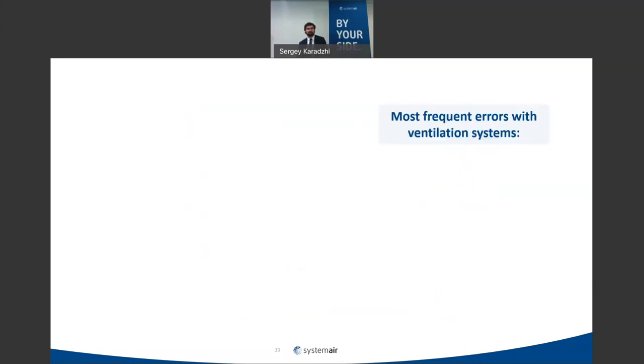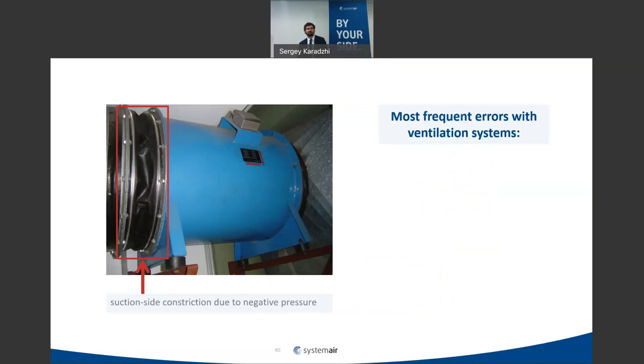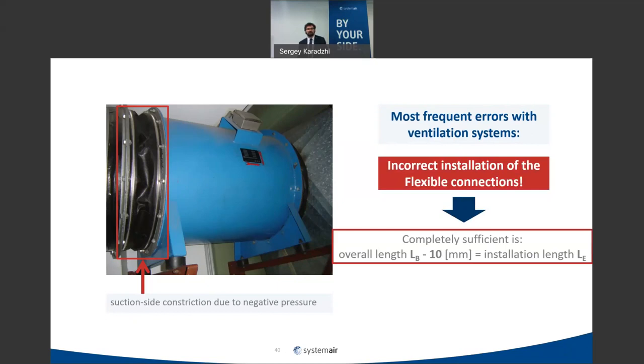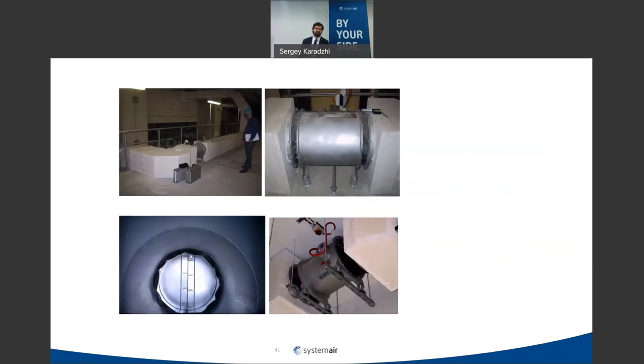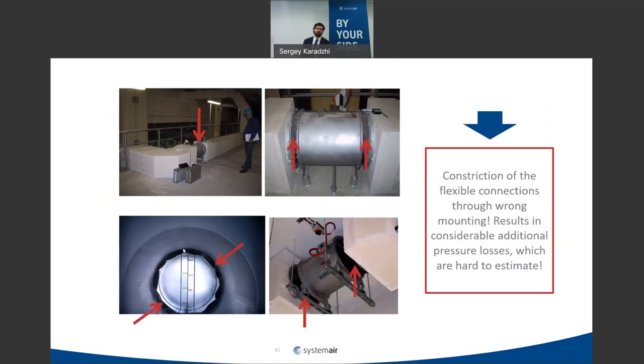Another bad installation example involves flexible connections that are sucked in because the user did not maintain the correct distance between the duct and the fan on the suction side. This creates additional losses that could easily be avoided by using the correct length between duct and fan.